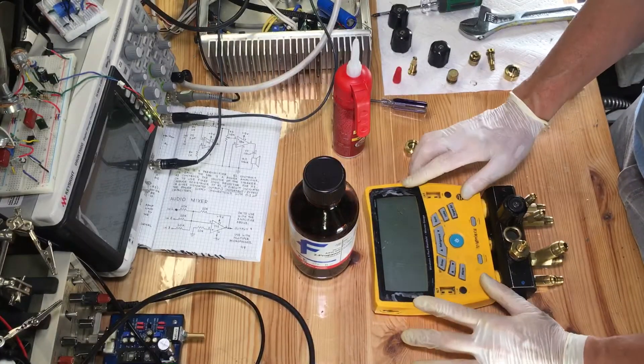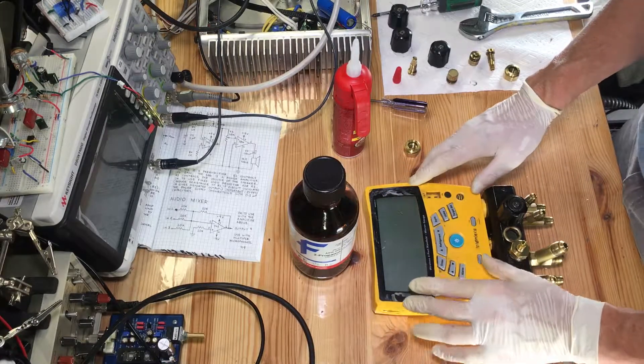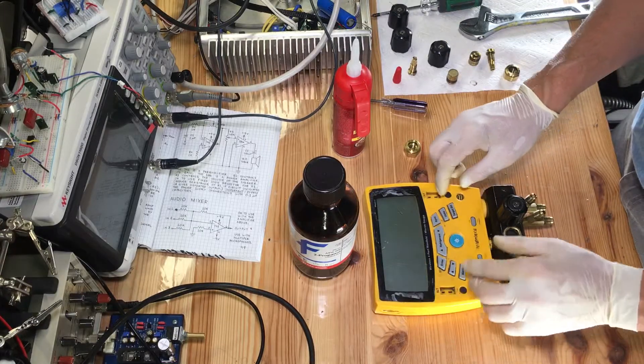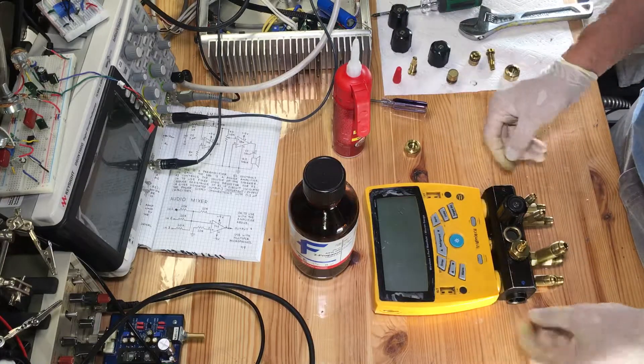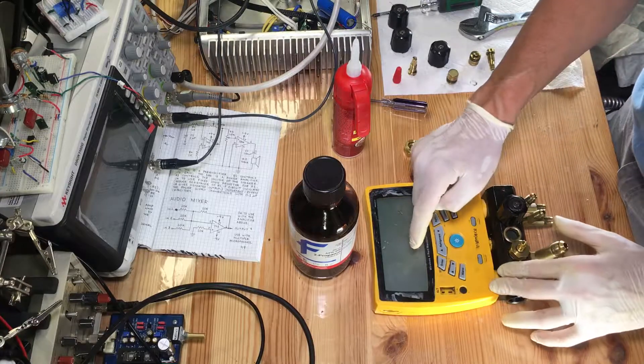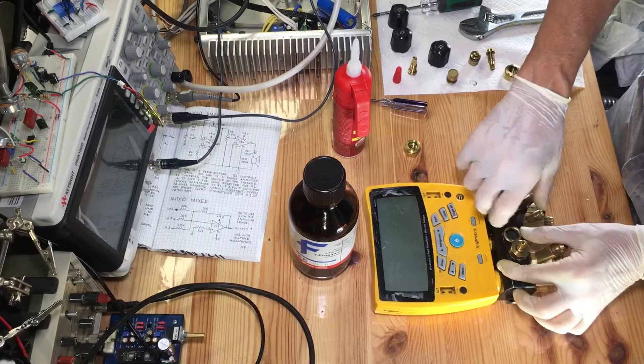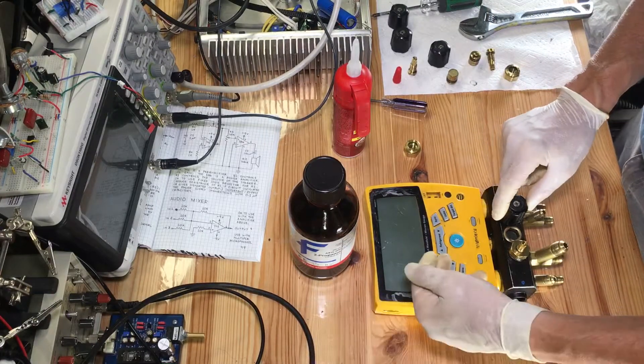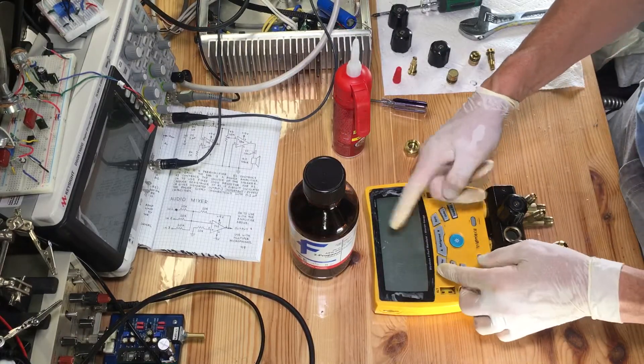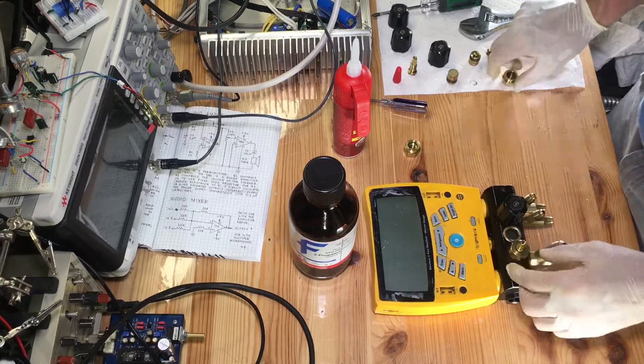Every one of them right out of the box, when I tried to draw a deep vacuum down below 100 microns, somewhere around three or four hundred microns, I would notice the vacuum stabilizing off there and leaking. Even if I disconnected the hoses and sealed everything off, when you would read your micron meter it would still pop off. When you would move your valves, you would notice it jump up several hundred microns or a few microns. You'd wiggle back and forth, you would see the micron meter move up. It was all leaking past these valves.